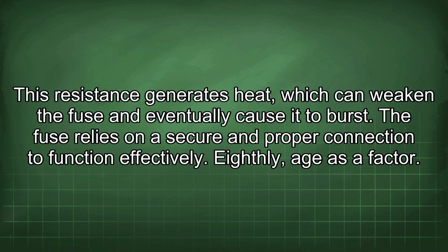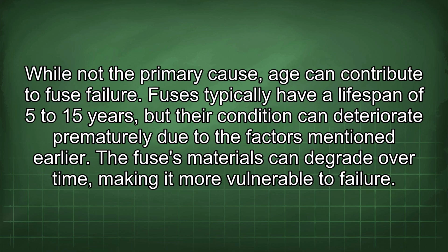Eighthly, age as a factor. While not the primary cause, age can contribute to fuse failure. Fuses typically have a lifespan of 5 to 15 years, but their condition can deteriorate prematurely due to the factors mentioned earlier. The fuse's materials can degrade over time, making it more vulnerable to failure.